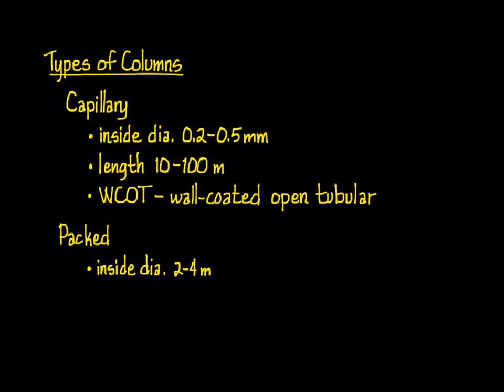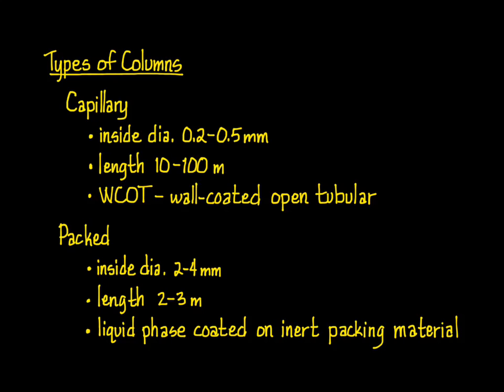Packed columns, in contrast, have larger inside diameters, usually in the 2 to 4 millimeter range, and are considerably shorter, just a few meters. They're called packed because they're filled with small particles in an inert packing material, usually diatomaceous earth, on which the liquid phase is coated. The packing is porous, and the carrier gas can move the mixture being analyzed through and around the particles as it travels through the column.